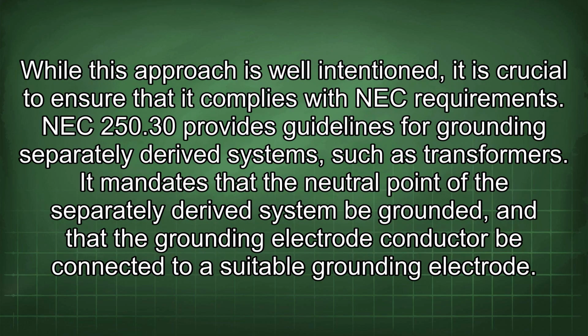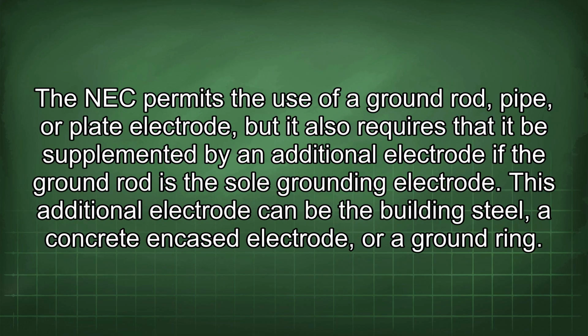While this approach is well intentioned, it is crucial to ensure that it complies with NEC requirements. NEC 250.30 provides guidelines for grounding separately derived systems, such as transformers. It mandates that the neutral point of the separately derived system be grounded, and that the grounding electrode conductor be connected to a suitable grounding electrode. The NEC permits the use of a ground rod, pipe, or plate electrode, but it also requires that it be supplemented by an additional electrode if the ground rod is the sole grounding electrode. This additional electrode can be the building steel, a concrete encased electrode, or a ground ring.